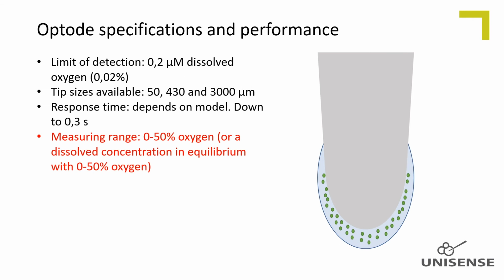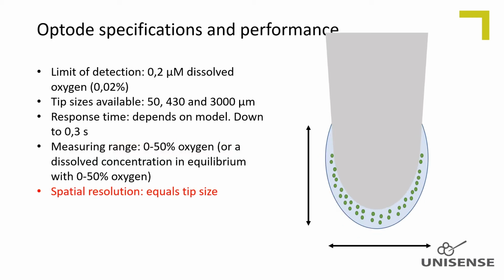At partial pressures more than 2.5 times atmospheric partial pressure, the relative change in fluorescence with oxygen change is so low that it compromises the accuracy. The recommended measuring range is therefore set to 0 to 50% oxygen partial pressure. The spatial resolution is defined by the length of the polystyrene/dye matrix on the glass fiber tip. This length is about the same as the tip diameter. Thus, the spatial resolution equals the tip diameter.